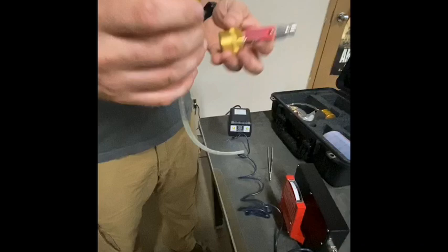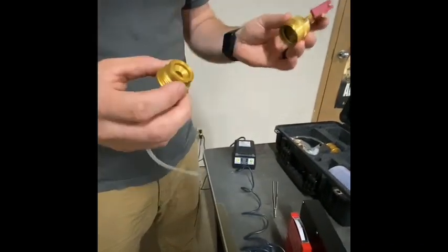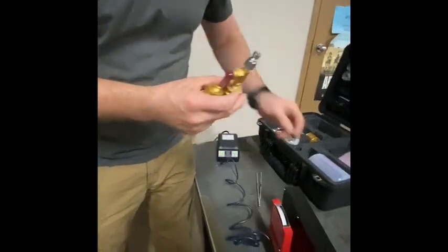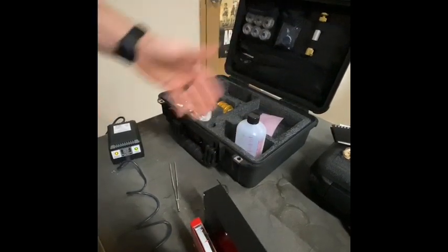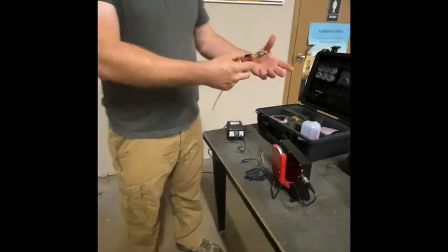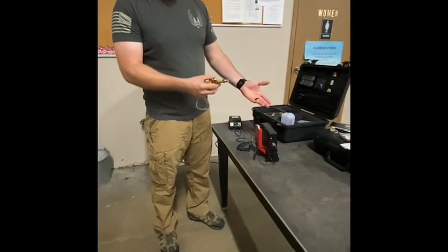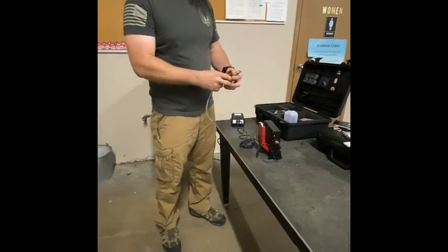Now, before you do that, you would want to flush 1 liter of fuel through this system to make sure that all contaminants are out of it. And you just put it in this bottle right here, or this is a 500 milliliter bottle. But you put it into a container, and then you would put the container into a bad fuel container. You don't put it into a fuel tank somewhere. That's just making sure that contaminants are out of the system.